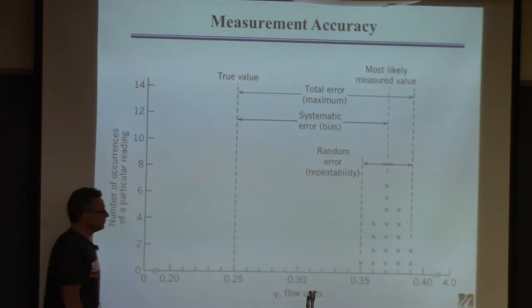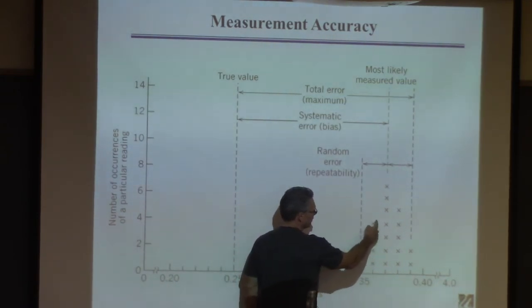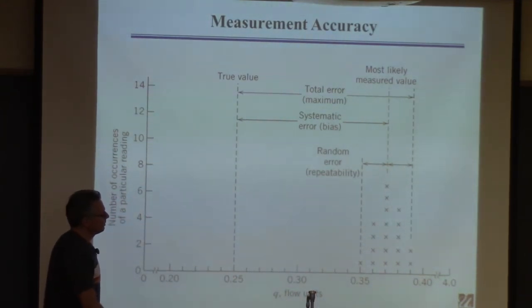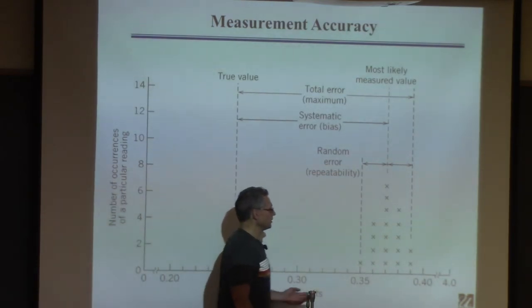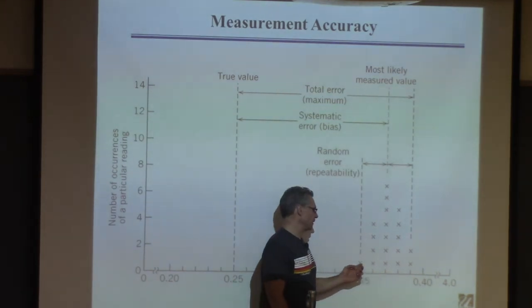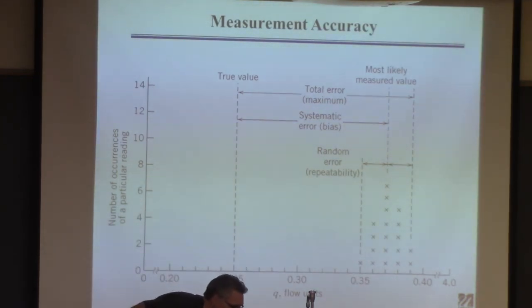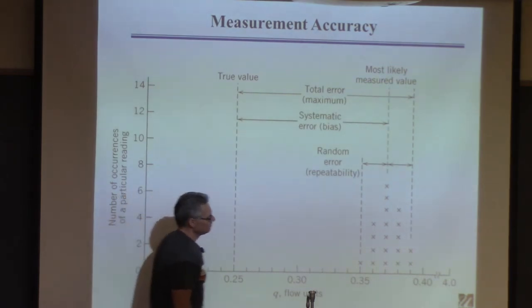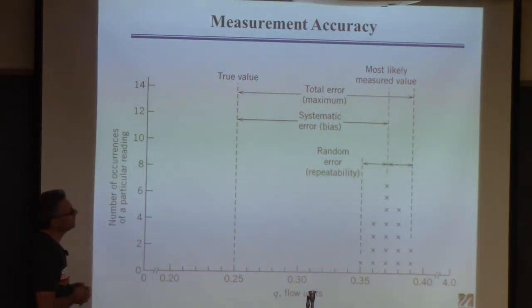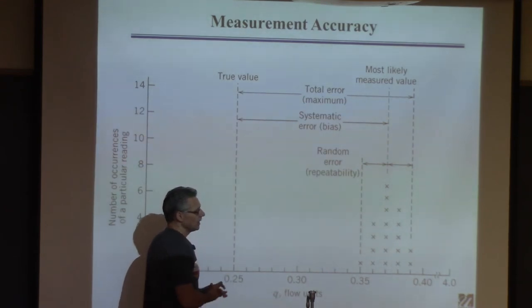So if you measure — this is the number of occurrences — you got this number 0.35 one time, this four times, so on and so forth. You can see from this there's an issue of random error. Because there's noise in the flow and the instrument, you might measure this one time and this one time. But if it's a good device, there's some kind of bell curve here. If this random error is small, it's just something you have to deal with and it should be okay. If the randomness is huge, then you've got a major problem.